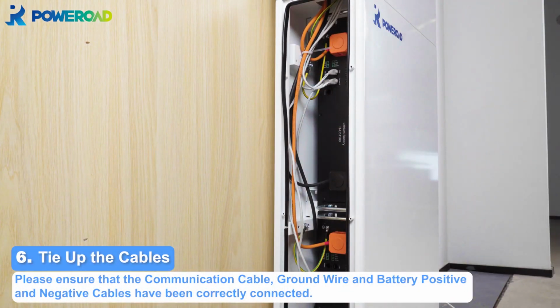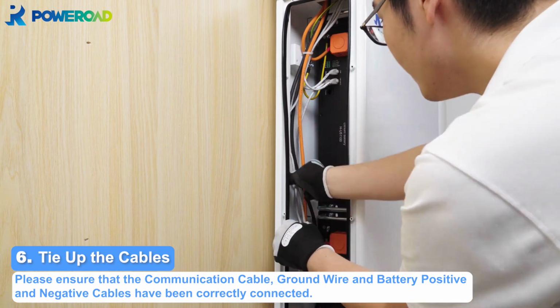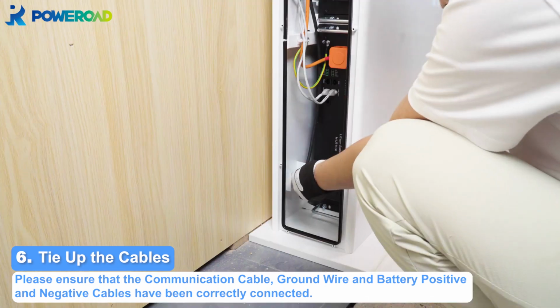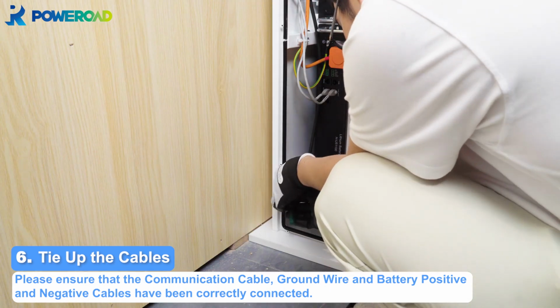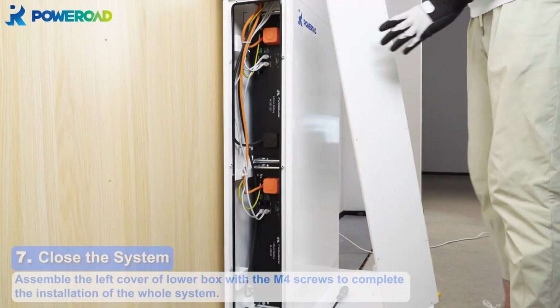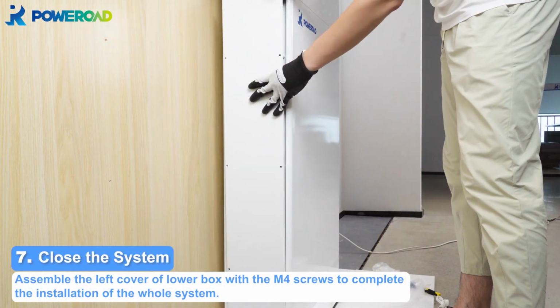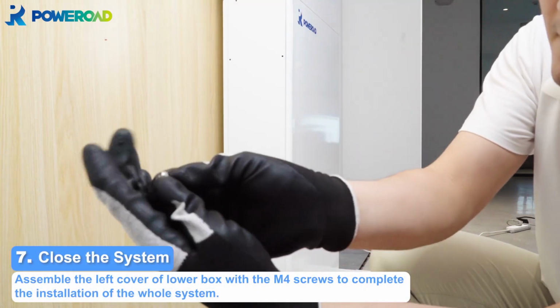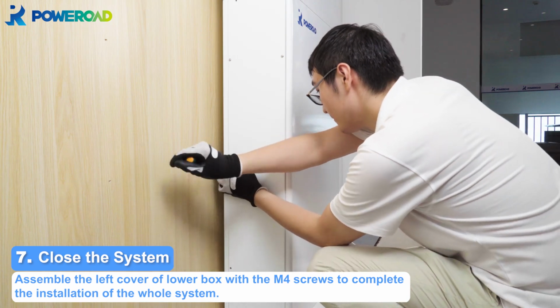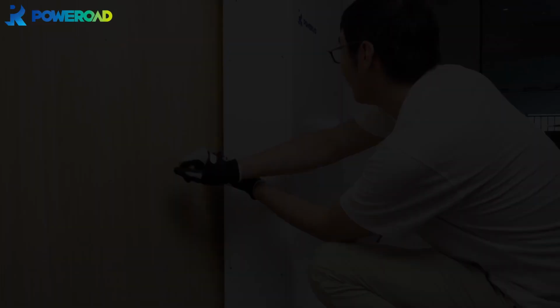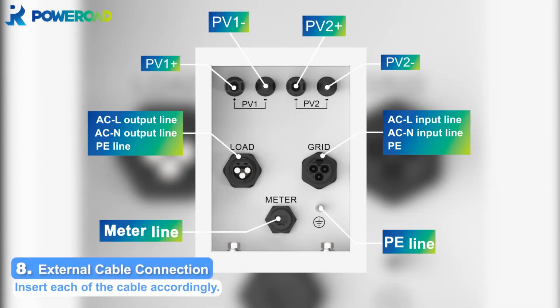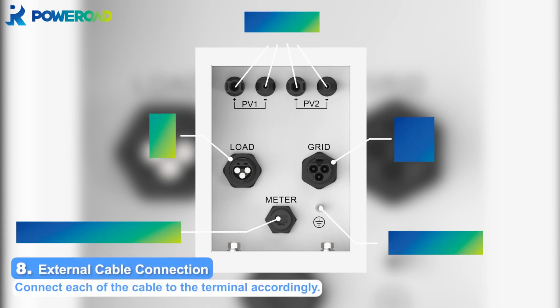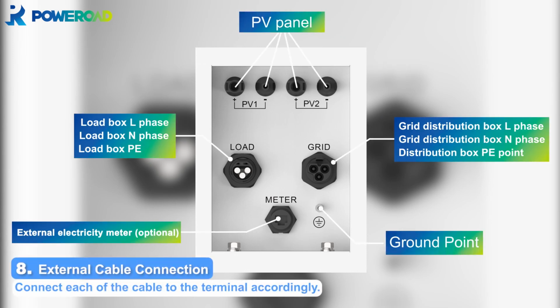Please ensure that the communication cable, ground wire, and battery positive and negative cables have been correctly connected. Assemble the left cover of lower box with the M4 screws to complete the installation of the whole system. Insert each of the cable accordingly. Connect each of the cable to the terminal accordingly.